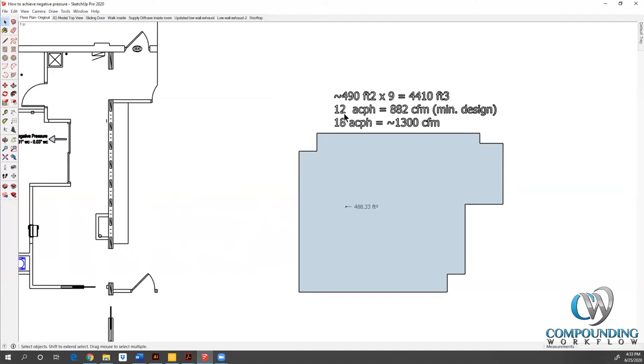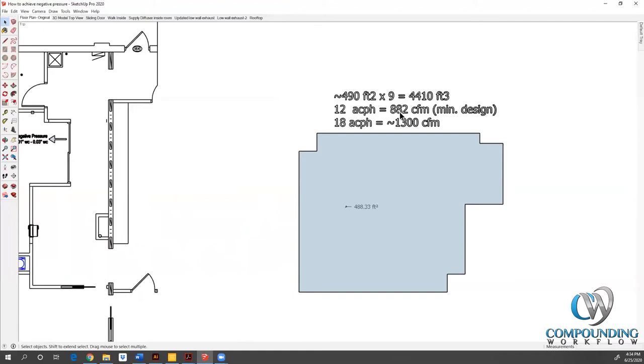I know that in an 800 non-sterile hazardous compounding room, I must maintain a minimum of 12 air changes per hour. So what I actually do is I take the 4410, multiply it times 12, and then divide it by 60. 60 is the number of minutes in an hour. That number never changes. It's a constant factor in our equation. So again, square footage times wall height equals cubic feet. Cubic feet multiplied by the desired number of air changes divided by 60.